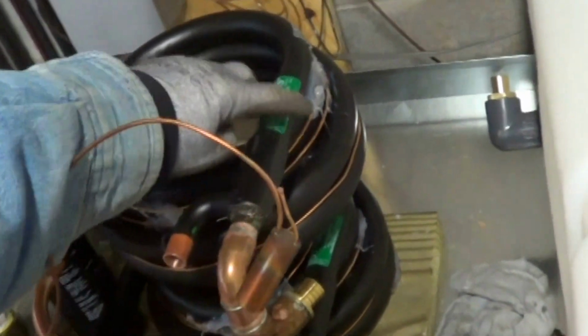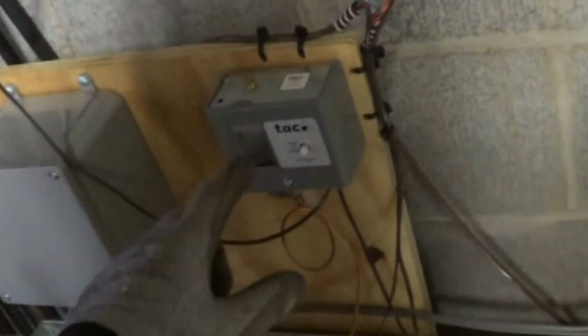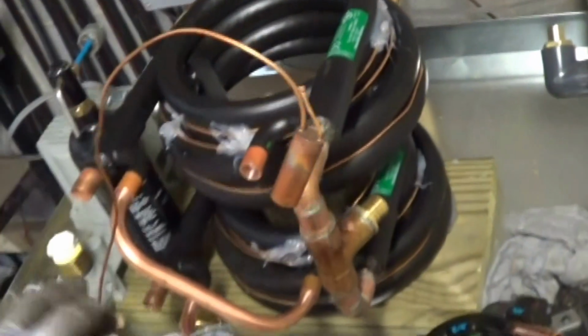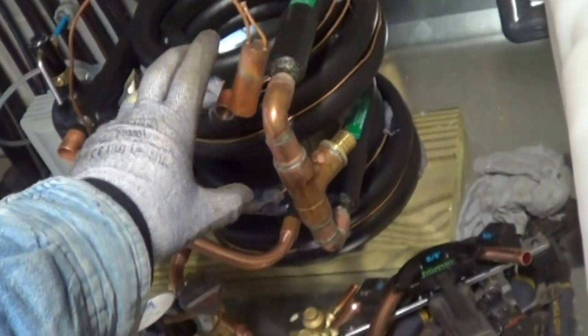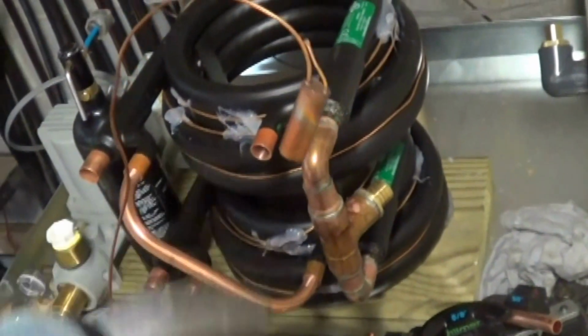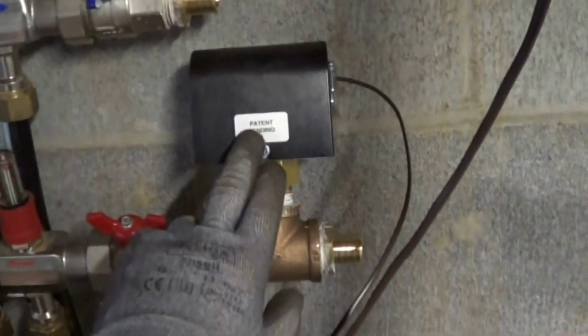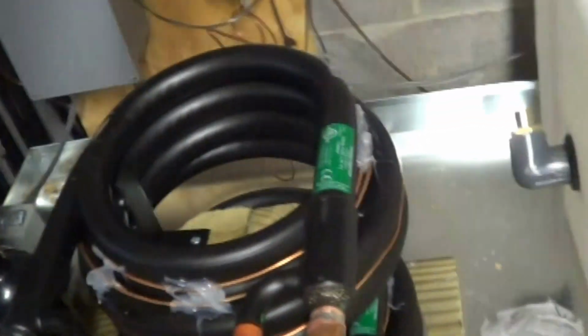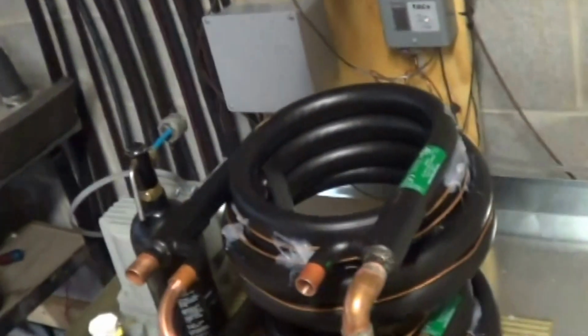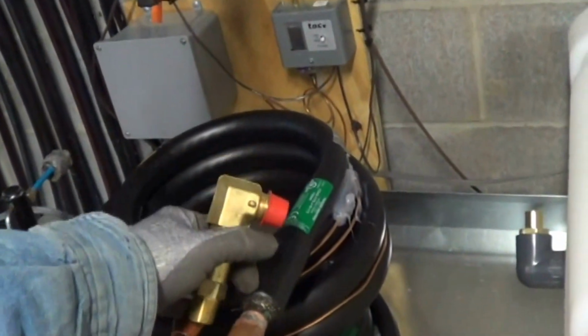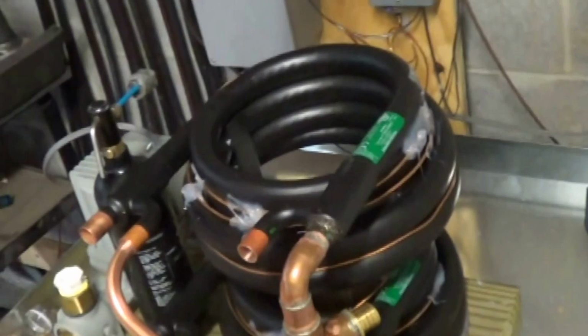So I'm doing a freeze thermostat, which is right here. That way, if this for some reason went to cooling, we're not gonna freeze and bust it all up. And also doing a flow switch. Also, since we're having isolation valves, there's always the potential the customer could screw it up and not pump it down into the condenser, and then say pump all the refrigerant into the barrel, and then the barrel heats up, and then you end up blowing something up.